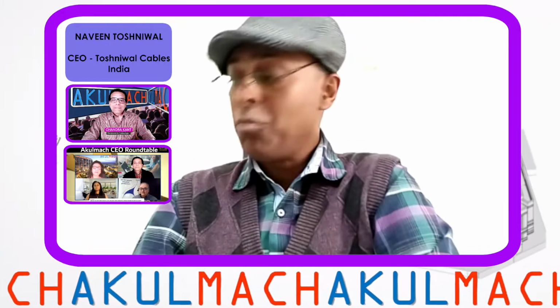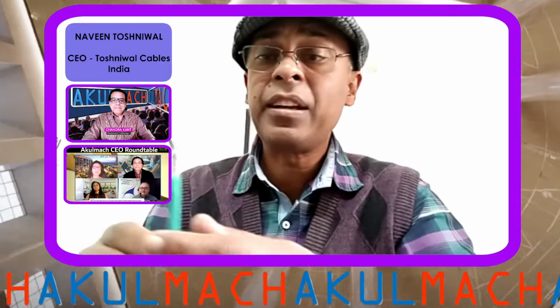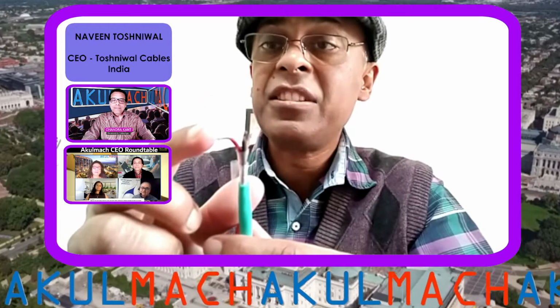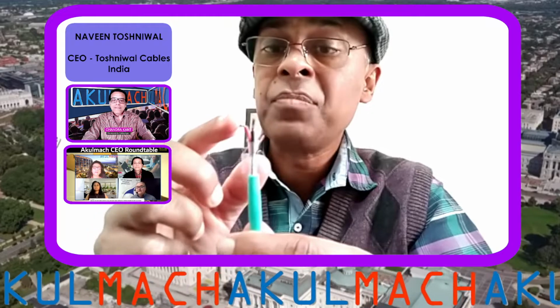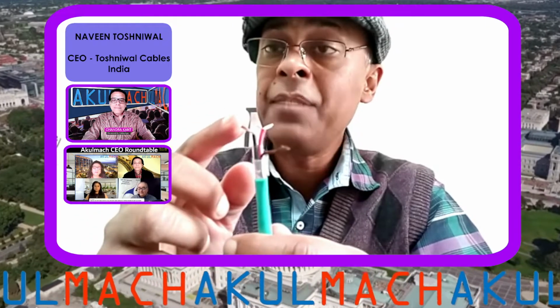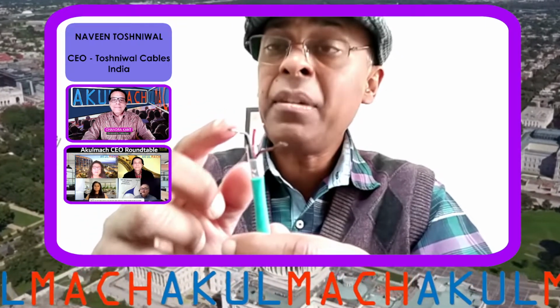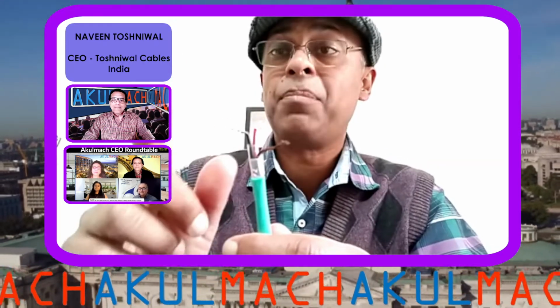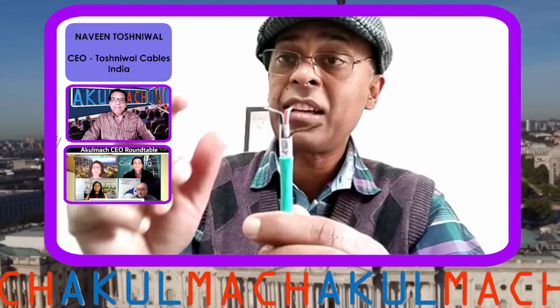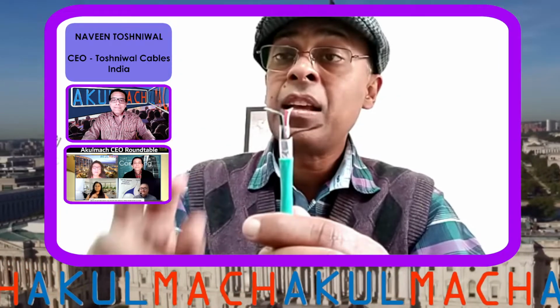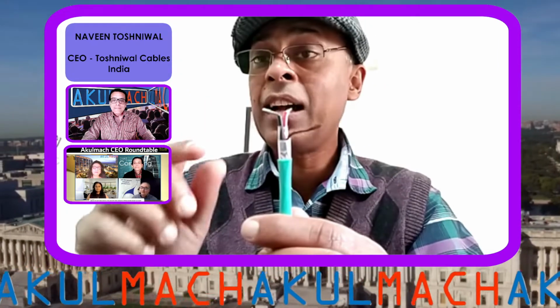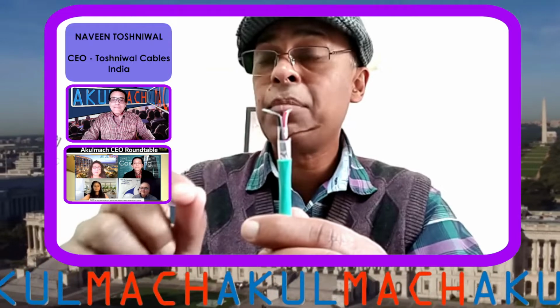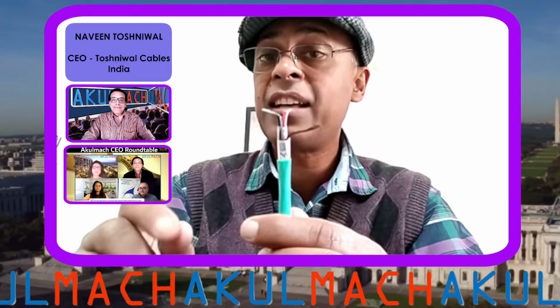Now, the most important point is that the conductor used inside the cable has to be of very good quality so that the EMF characteristics match those of the thermocouples. Because remember, in a thermocouple, the wires are very costly. They are the original chromel alumel or platinum rhodium wires. They are actually very costly.